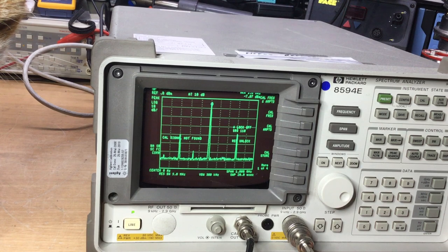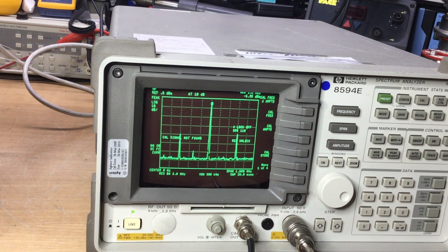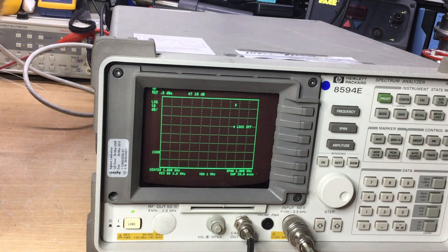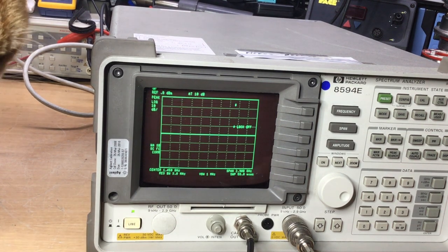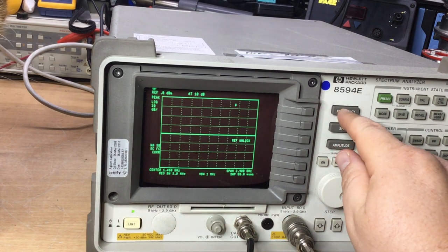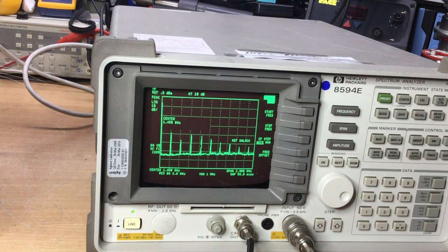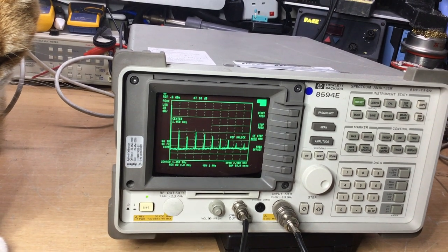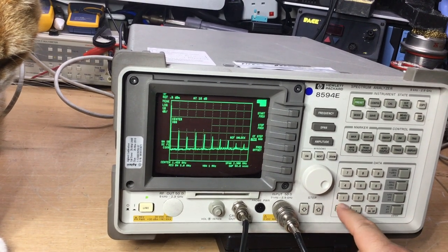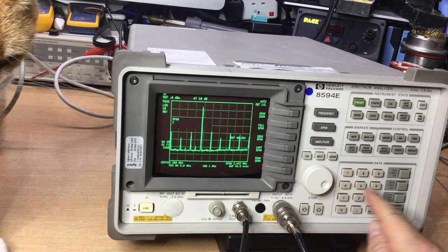Yeah, cal signal not found, it says, so it can't see the signal that comes out. Now this is a 300 megahertz signal, from what I understand. So we'll need to look at that to find out whether there's actually a calibrate signal coming out. Now we can actually try and do that.